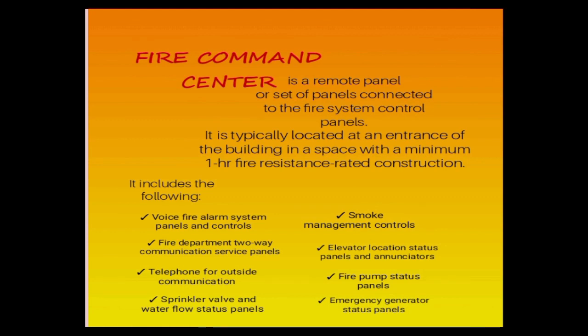It is typically located at an entrance of the building in a space with a minimum 1-hour fire resistance rated construction. It includes the following: voice fire alarm system panels and controls, fire department two-way communication service panels, telephone for outside communication, sprinkler valve and water flow status panels, smoke management controls, elevator location status panels and annunciators, fire pump status panels, and emergency generator status panels.